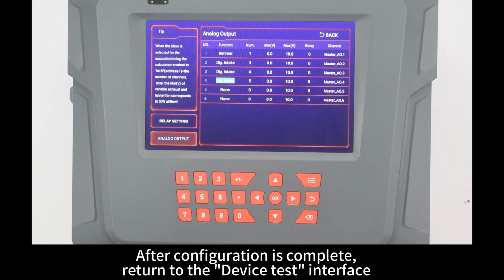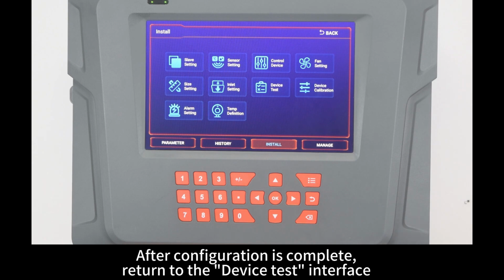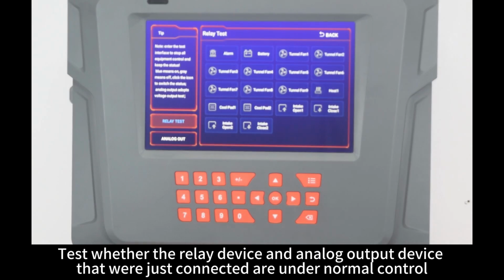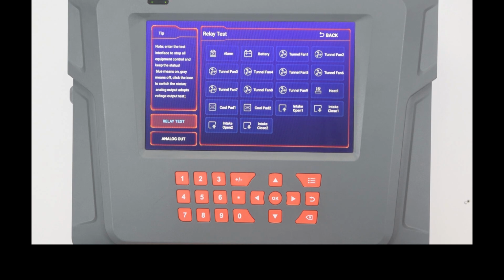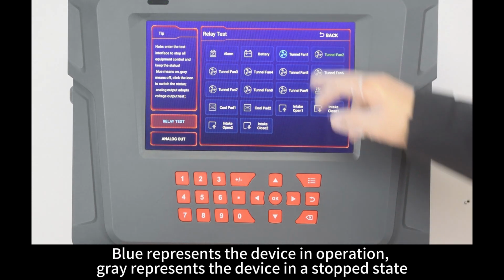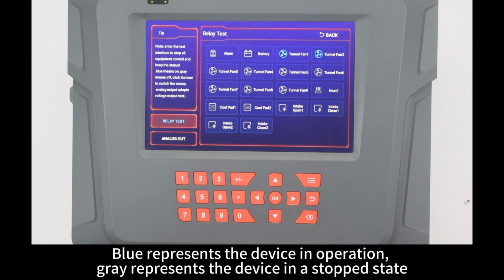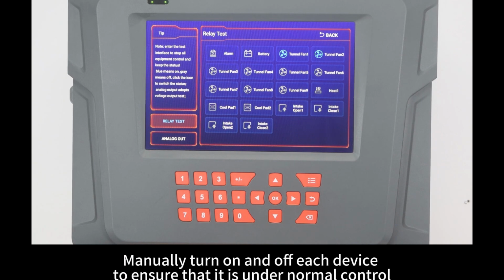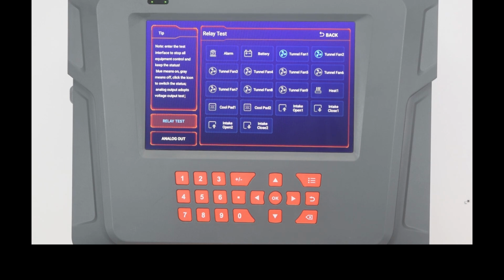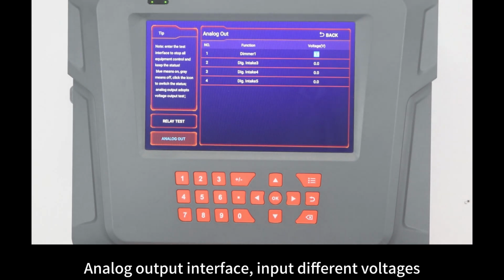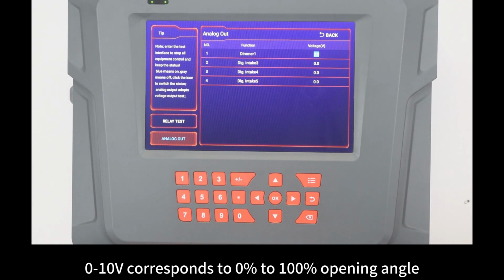After configuration is complete, return to the device test interface. Test whether the relay device and analog output device that were just connected are under normal control. Blue represents the device in operation, gray represents the device in a stop state. Manually turn on and off each device to ensure that it is under normal control. In the analog output interface, input different voltages. 0 to 10 volts corresponds to 0% to 100% opening angle.